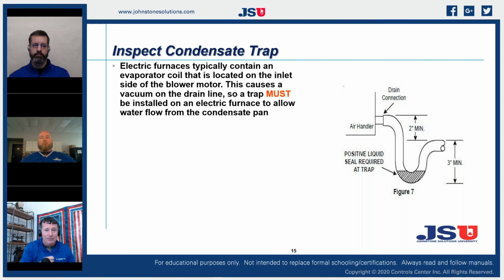And I've had that. I've had guys do installations, go, man, I am pulling water out of my trap and it's getting all over my coil. It's getting all over my cabinet. And I go, what? You got high static pressure. And I go, oh, really? I was like, yes. You got more than 1/2 inch and it's pulling it right out of your trap. So verify your pressures and verify that you have the proper trap on it.